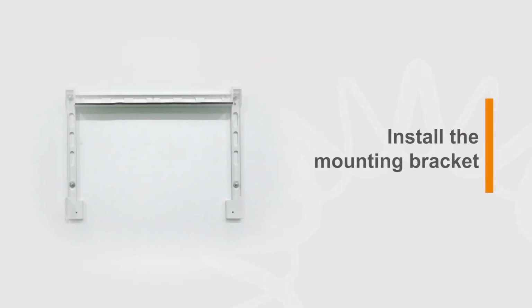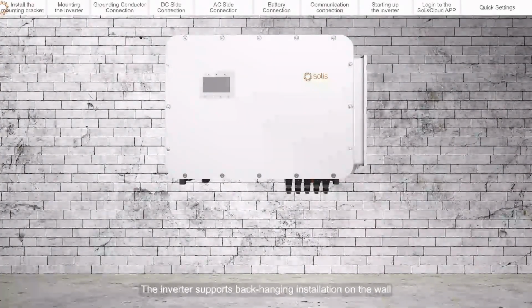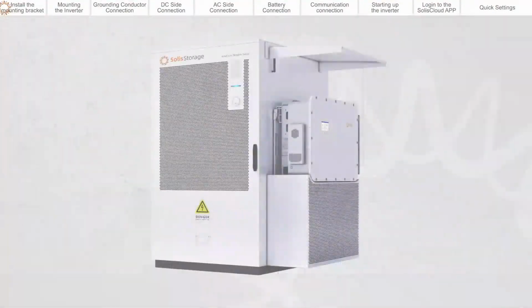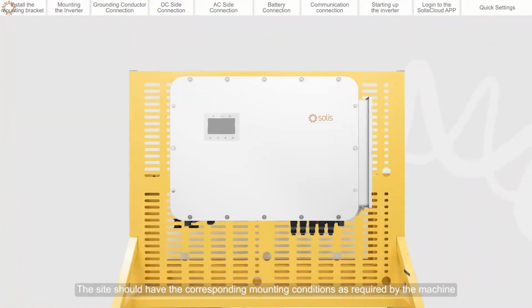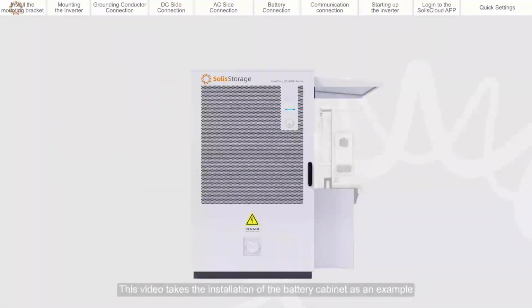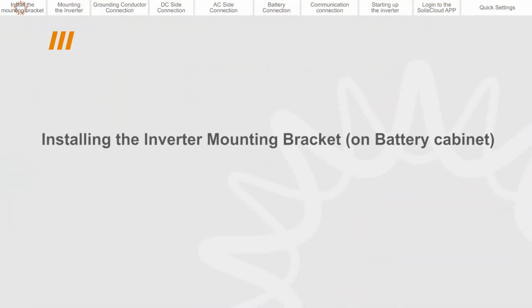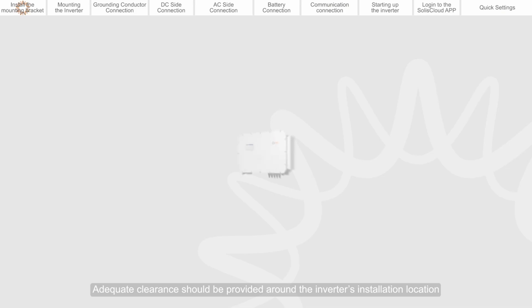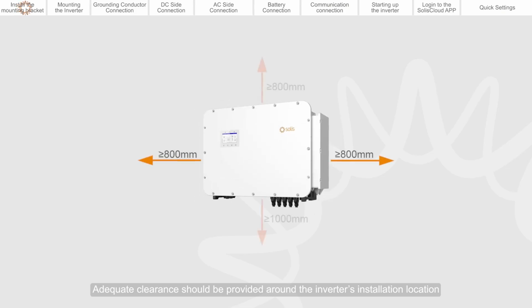Install the mounting bracket. The inverter supports back-hanging installation on the wall, battery cabinet, and battery rack. The site should have the corresponding mounting conditions as required by the machine. This video takes the installation of the battery cabinet as an example. Adequate clearance should be provided around the inverter's installation location.